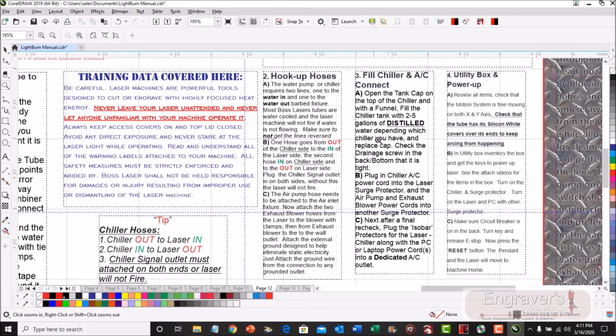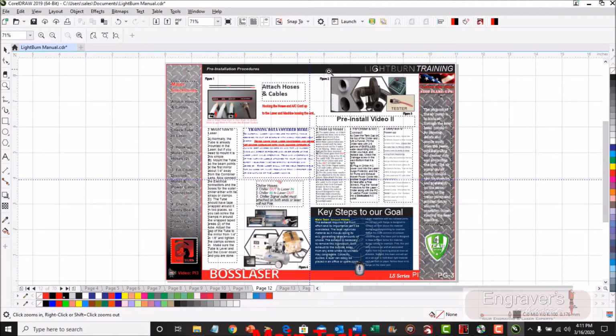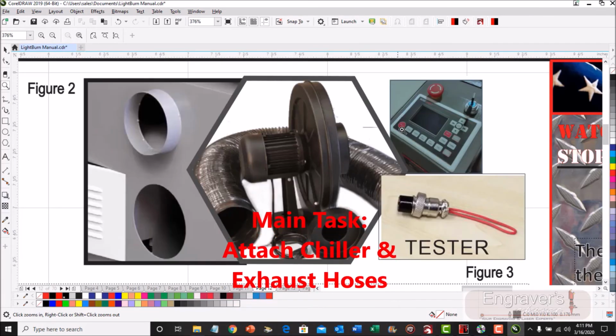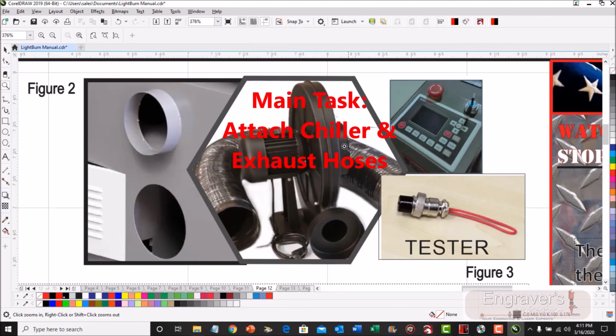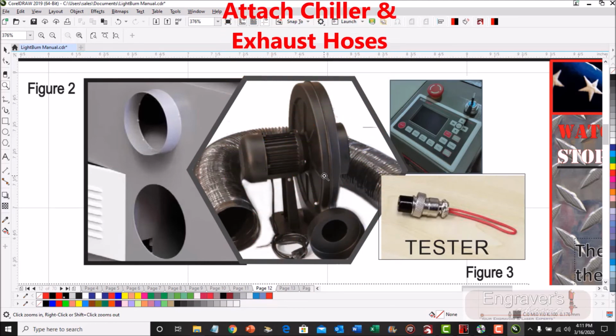Then you're going to fill the chiller up with distilled water and make sure that the AC is plugged in to the unit. So put your cable into the back of the unit. The other thing I do at this point is I inspect the utility box, make sure that items are in the utility box. You'll get a checklist here in the next coming section. Then I go ahead and inspect the back of the air exhaust and I turn it on.